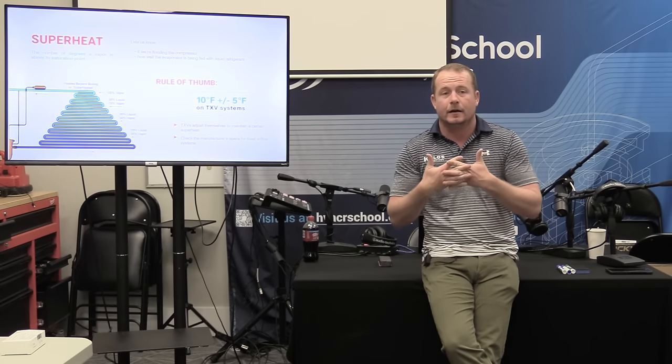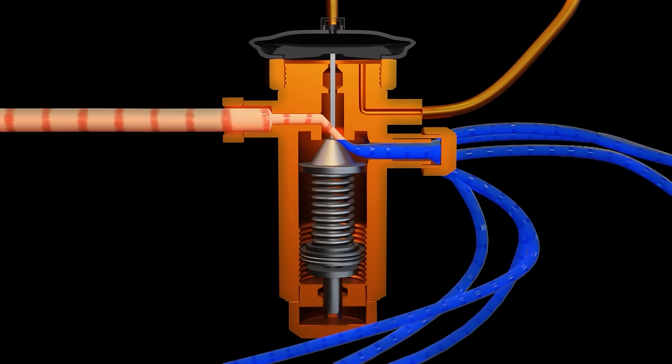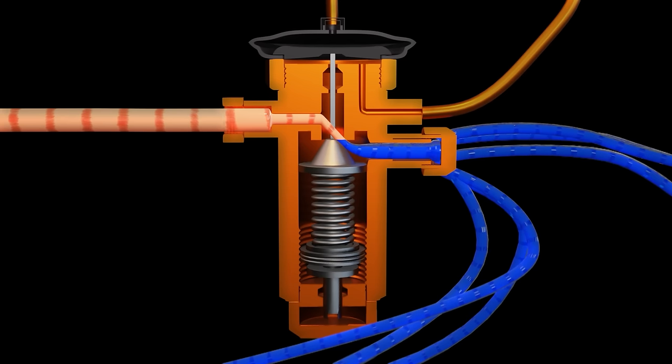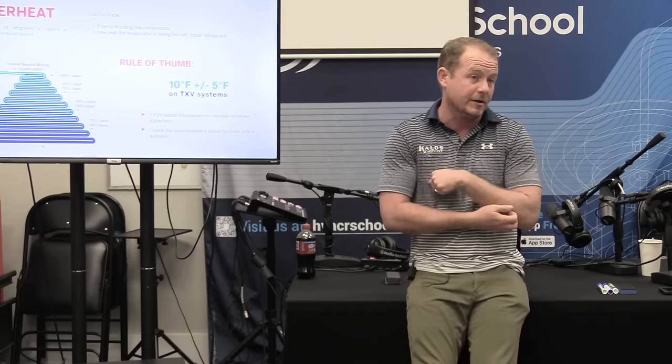When we say boiling, boiling is another word for — we use it synonymously with evaporating. They're not exactly the same; we really should call it boiling rather than evaporating. Regardless, it's a change of state from liquid to vapor. And when we feed an evaporator coil, what goes into that metering device? Liquid refrigerant — it needs to be all liquid refrigerant. That's one of our primary goals. That's why we measure subcool.